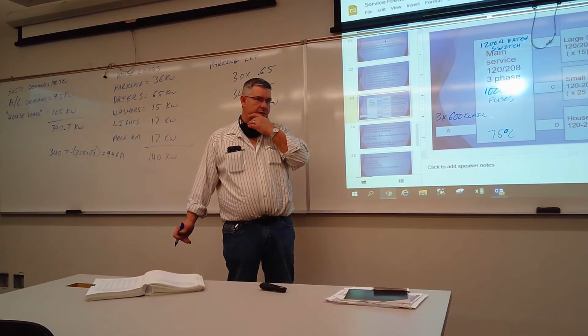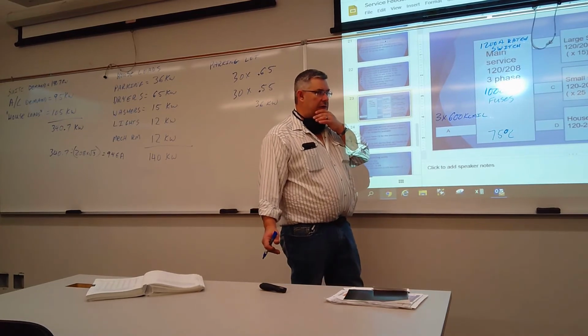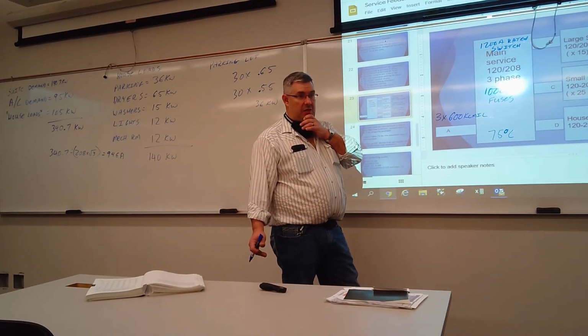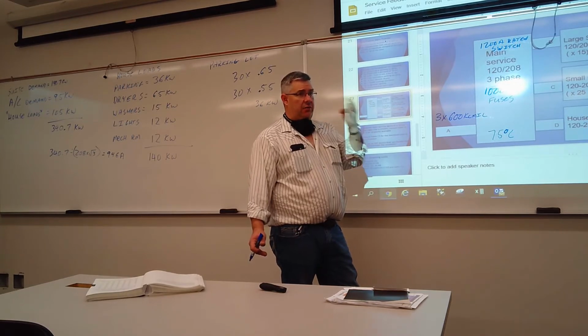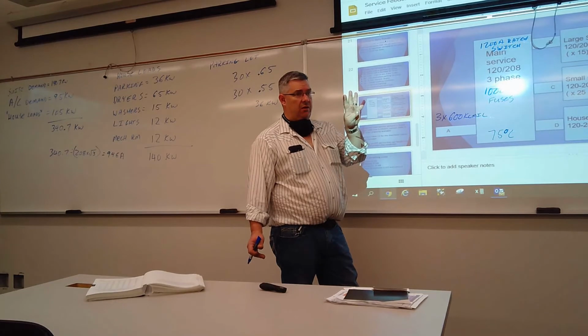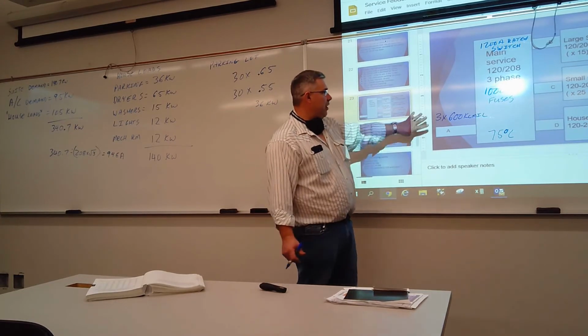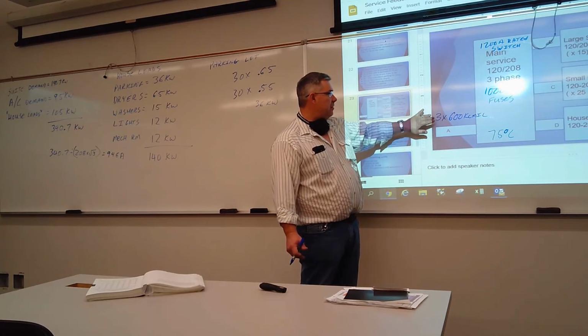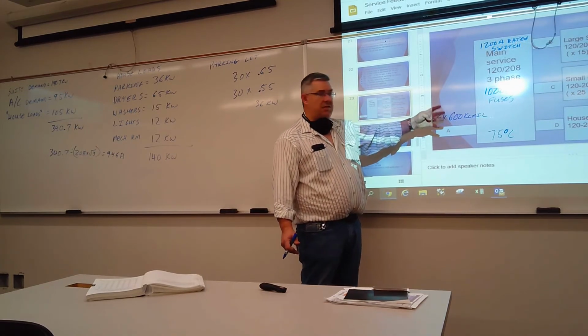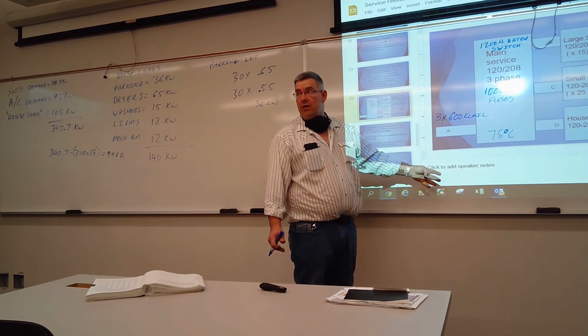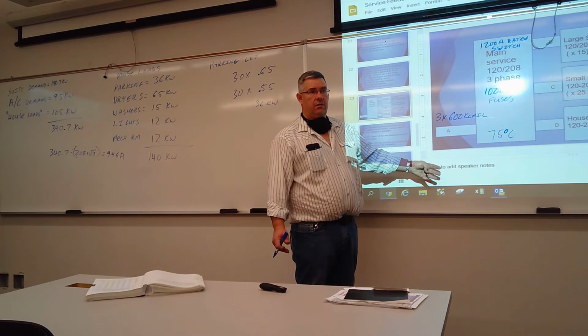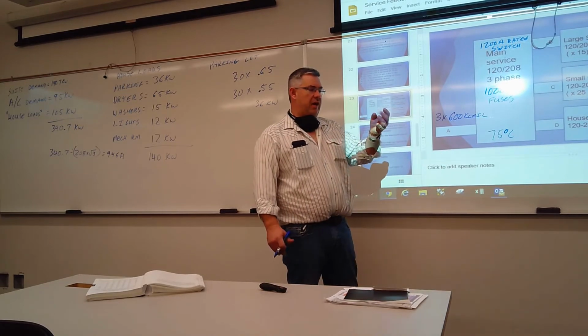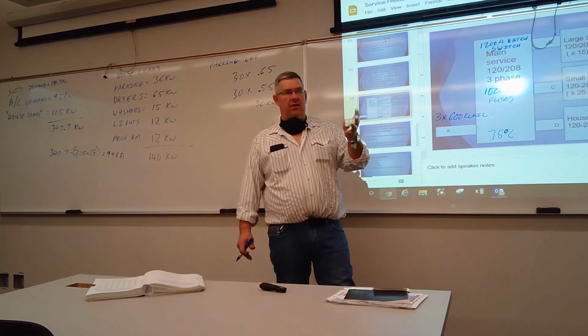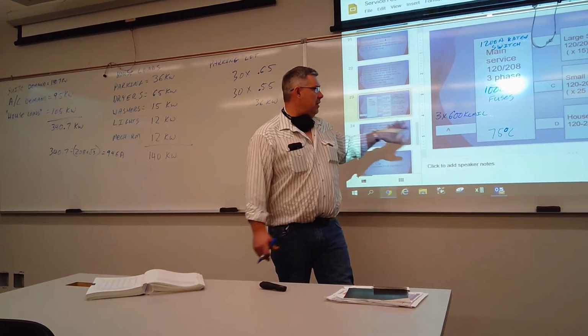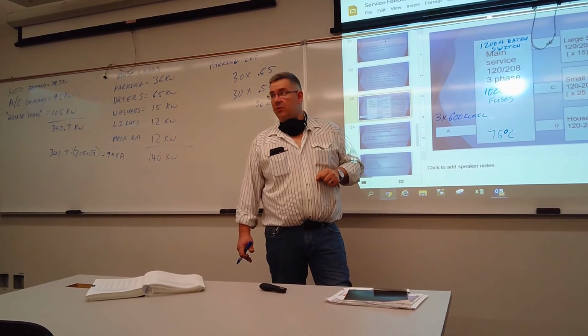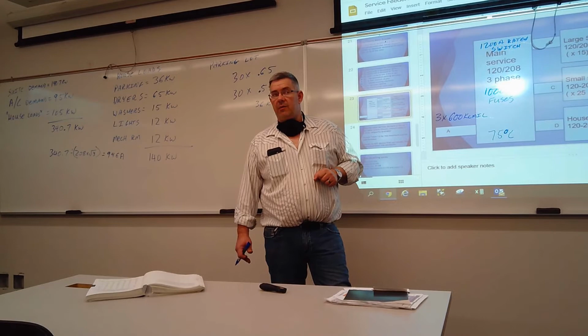You saying 9? Conductors, I think so. It's a 120/208, so it's a Y service, so we need 3 hots, 3 phase conductors, and a neutral to make it work, right? We then split that into 3 runs. So we're gonna have 3 conduits with 4 600 kcmil conductors in each conduit. In each conduit, we're gonna have a red, black, blue, and white 600 kcmil conductor, and we're gonna need 3 of those to get up to the 946 amps that we needed. That making sense?